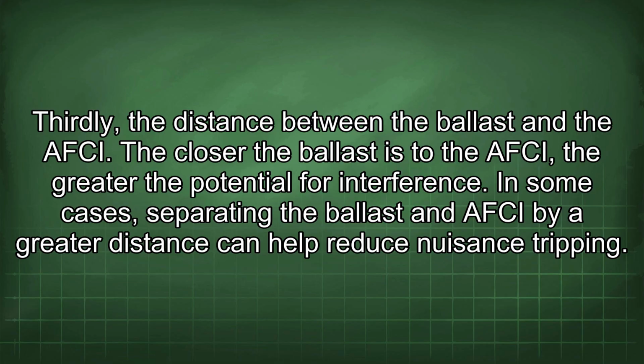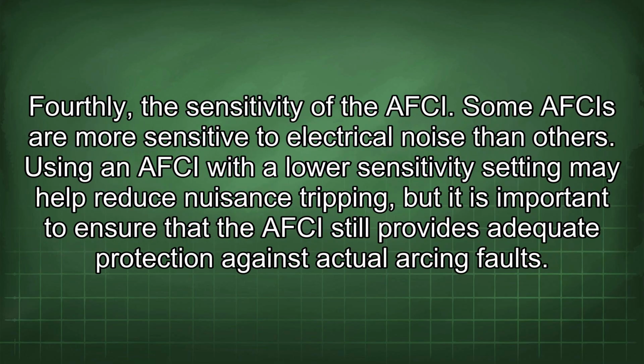Thirdly, the distance between the ballast and the AFCI. The closer the ballast is to the AFCI, the greater the potential for interference. In some cases, separating the ballast and AFCI by a greater distance can help reduce nuisance tripping. Fourthly, the sensitivity of the AFCI. Some AFCIs are more sensitive to electrical noise than others. Using an AFCI with a lower sensitivity setting may help reduce nuisance tripping, but it is important to ensure that the AFCI still provides adequate protection against actual arcing faults.